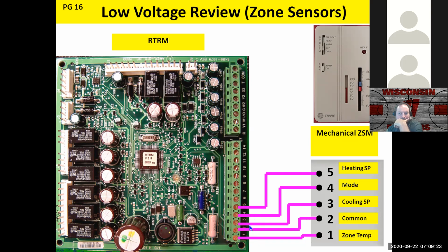Now, if you don't use 2, 3, 4, or 5, and you just leave the first 2 wires hooked up, what it will do is fall to a default of 71 degrees heat, 74 degrees cool, and fan on. So if you just hang a 10K sensor on terminal 1 and 2 of this board, it will maintain that 71 degrees heat, 74 degrees cool forever. Which is good for temporary operation.